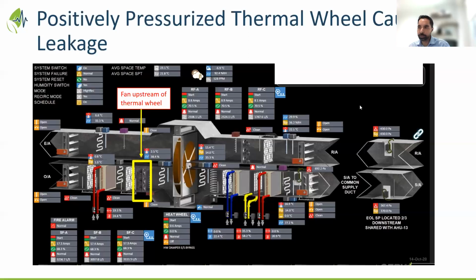So the units are generally sized to have a purge, which is purge from the supply to the exhaust. So that ensures that you have a discharge from the supply to the exhaust side. Your flow of the air is from the supply to the exhaust side, and also when they're balanced, to make sure that purge exists in these units. So obviously with operations, things could change, and that's why we always recommend to test these systems to make sure that there is no cross contamination.